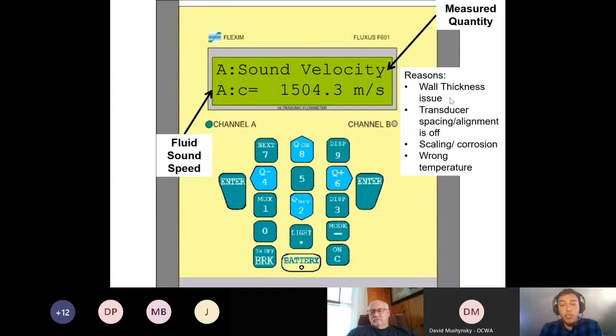So maybe there's so much scaling in the pipe that the wall has actually increased a quarter inch, half inch. What we would recommend there is you slowly start to increase that wall thickness until you can tie down the sound speed. It could also be a transducer spacing and alignment issue. Make sure that your transducers are level with each other and the spacing is appropriate. Like I said, it could be scaling, or it could be the wrong temperature. Maybe the medium is actually at a higher temperature than you thought.